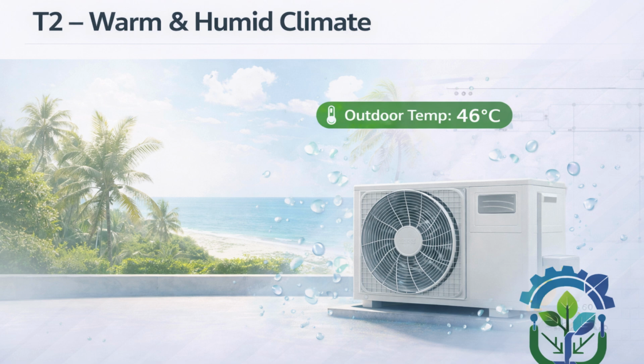Now let's understand what T2 is. T2 represents warm and humid climates. The design temperature is 46 degrees Celsius with higher humidity. T2 is typically used in tropical regions or coastal Southeast Asia. Compared to T1, T2 equipment handles heat better and is more robust. Now let's compare this to the Middle East reality.